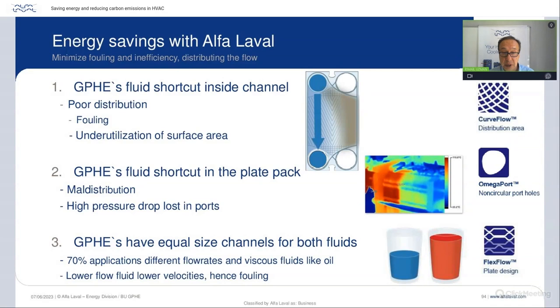These features enable us to deliver that performance. The second feature is the Omega port. You notice that the port shape of the Alfa Laval plates is actually non-circular. This reduces the maldistribution inside the plate pack, and it's also a bigger opening instead of a circular one, so that the pressure drop lost in the port, which is of course waste, is reduced. We want the pressure drop to be used for heat transfer. So the Omega port helps the performance and the energy savings immensely.